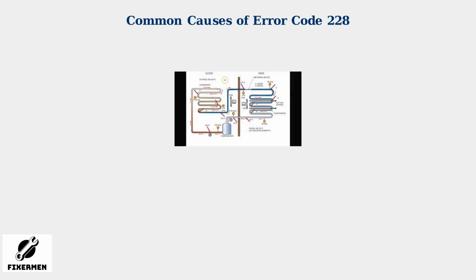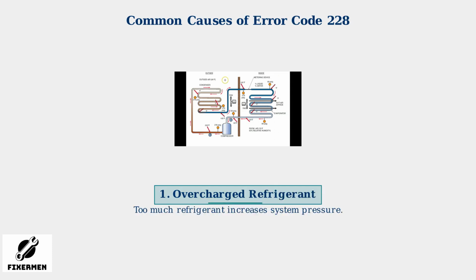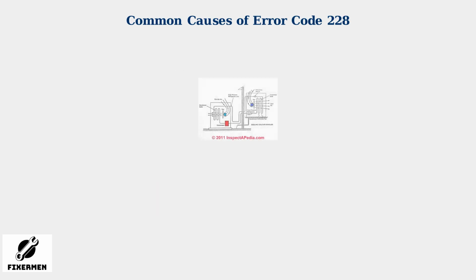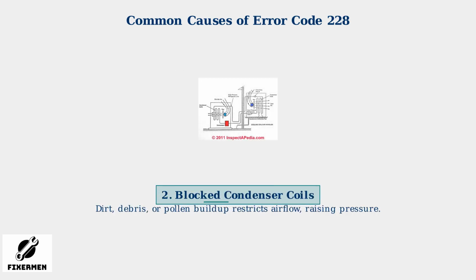Several factors can trigger Error code 228 in Lennox HVAC systems. Let's examine the most common causes. First, overcharged refrigerant. When too much refrigerant is added to the system, it causes excessive pressure in the lines, triggering the high-pressure switch to open. Second, blocked condenser coils. When dirt, debris, or pollen accumulates on the condenser coils, it restricts airflow. This prevents proper heat dissipation, causing refrigerant pressure to rise and activating the error code.